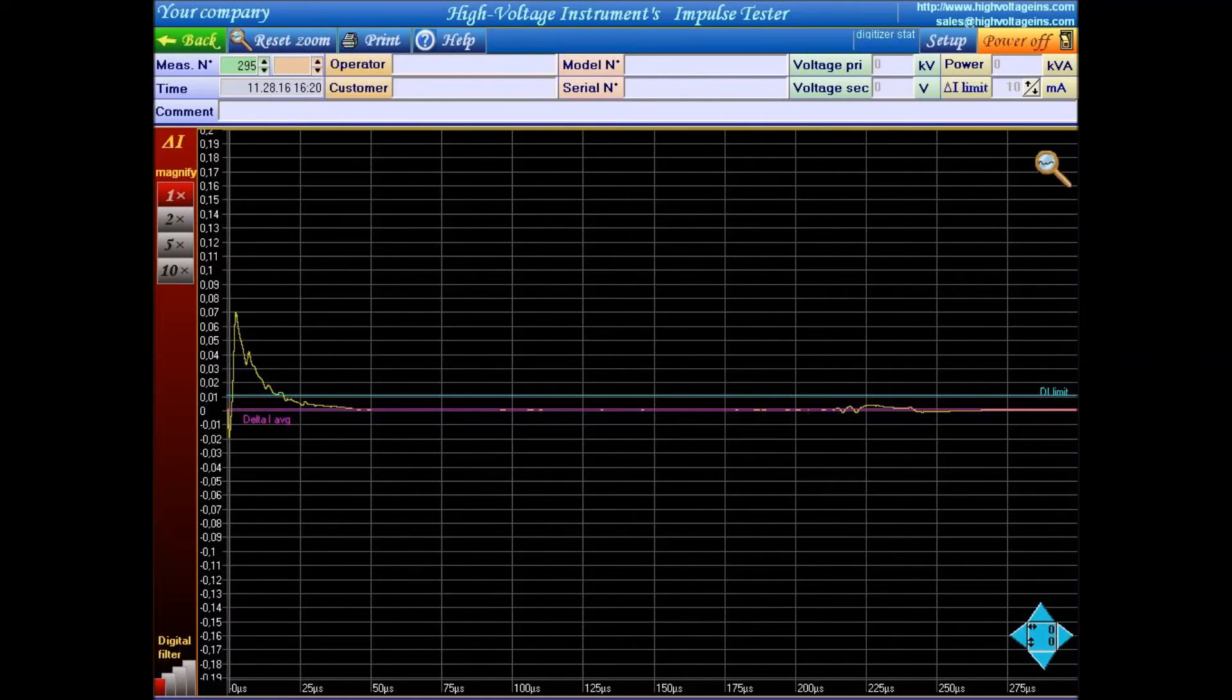The current difference will show the transformer is good or bad. We calculated from the transformer design. Single turn fault would increase the fault current wave by 10 milliamp, which is a blue line.